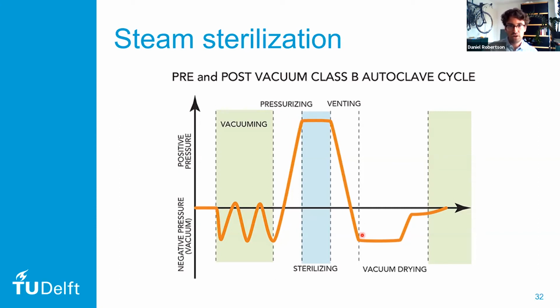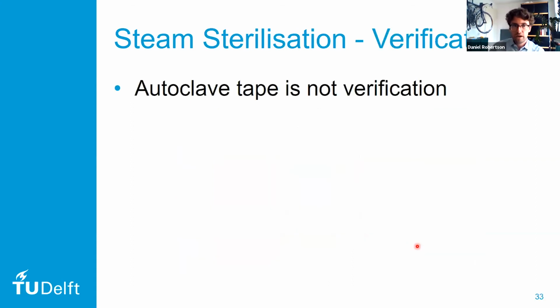Then, at the end of the cycle, the autoclave will pull another vacuum. Because of this vacuum, any remaining moisture on the instruments will be boiled off, and this means that the instrument packs will be dry at the end of the cycle. As mentioned, one of the big advantages of steam sterilization is that we can perform proper verification on the autoclave. So we can perform a few steps to see whether the cycle has been complete.